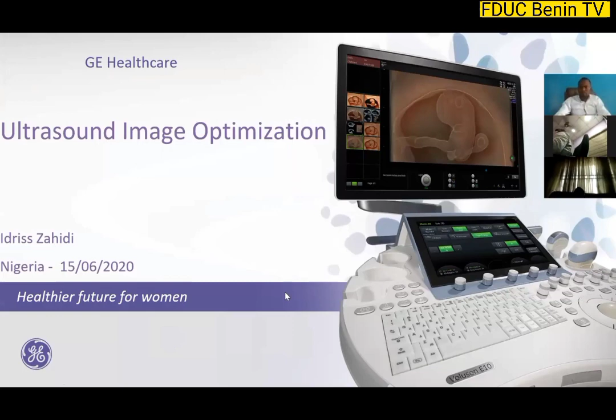Okay, first of all, as you all know, when you are scanning, the most important thing when you start is the choice of your probe, of course, but the whole ultrasound is related to the frequency. What frequency are we using when you are performing your exam? You know, because ultrasound has two features, speed and frequency. Frequency will impact directly your image resolution and your penetration. So frequency will either improve your image resolution, or it will give you more penetration.